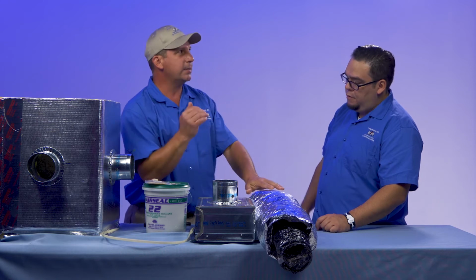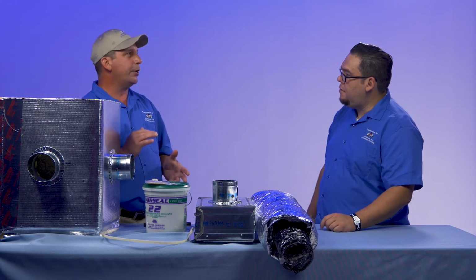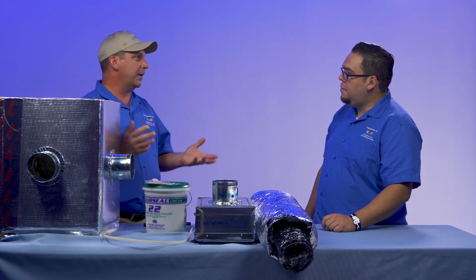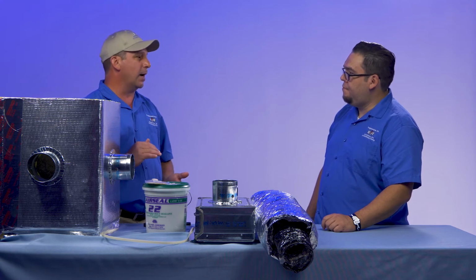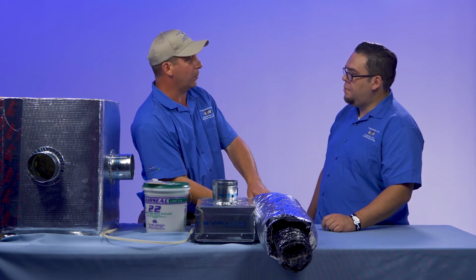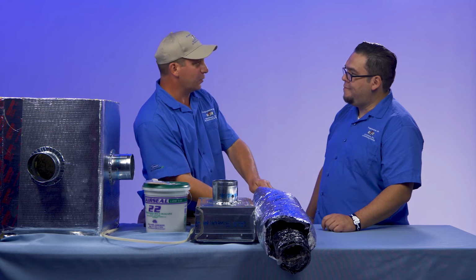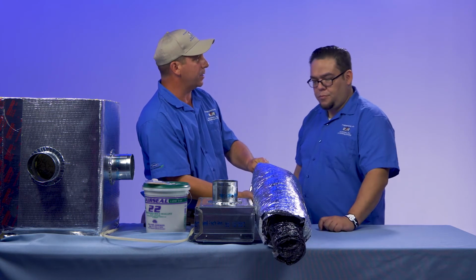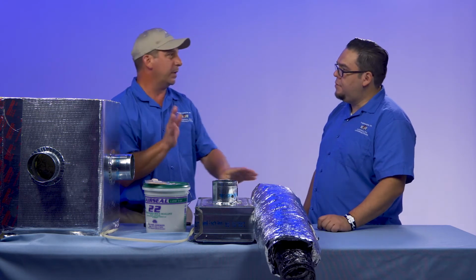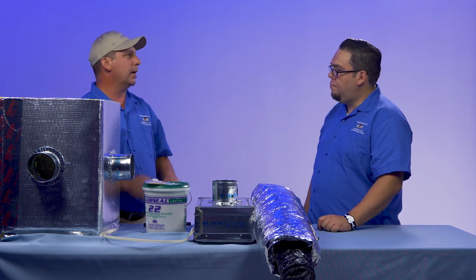So when you get that condensation around the outside, you get 140 degree temperature on a 95 degree day. That attic gets very hot. Right. And when you've lost that R rating with that cold duct, guess what happens? It starts to sweat. So then you've got the whole insulation underneath here soaking wet. That's not going to dry out. You're going to have to cut that out and replace it.